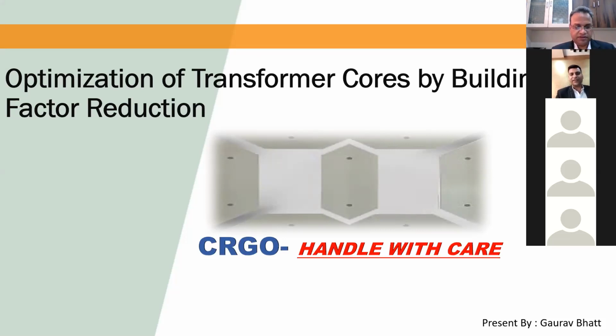CRGO magnetic steel is a very important part of the transformer core. The no load loss, or core loss, is also called fixed loss as it keeps happening during the life of the transformer. So the quality of the core plays a very important and crucial role in keeping the operating cost of a transformer, or the energy power sector system, to the minimum.